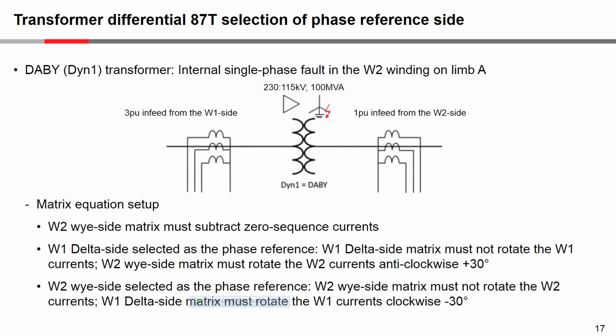So here we have that same transformer we had earlier, the DYN1. As far as the matrix equation setup is concerned, I just made a fictitious transformer for this, and we placed a fault on the A phase of the secondary side, the winding 2 side, and I just allowed 3 per unit in-feed from the winding 1 side and 1 per unit in-feed from the winding 2 side. That's just totally fictitious, to show a calculation. But the winding 2 side matrix must subtract zero sequence currents because it's a delta Y transformer, and remember on the Y side zero sequence currents can flow which are trapped in the delta, so the Y side needs to have the zero sequence subtraction.